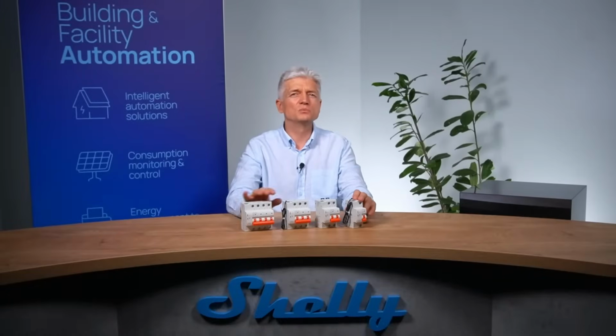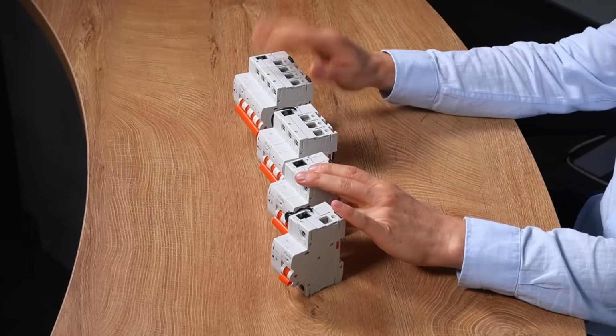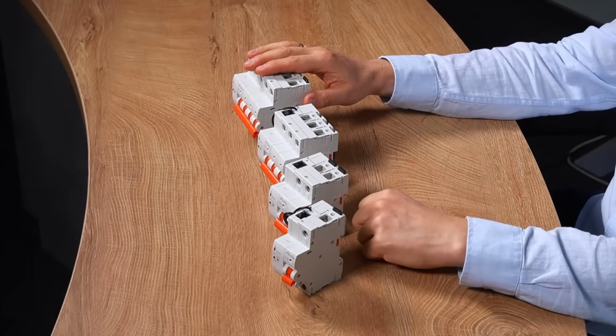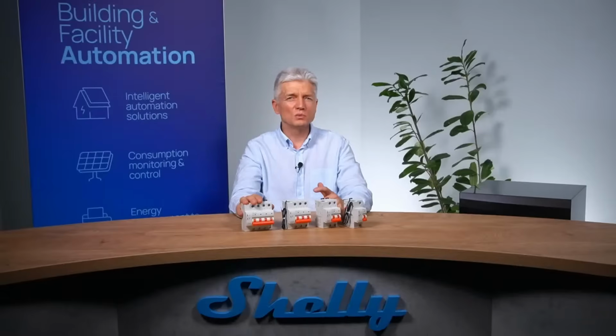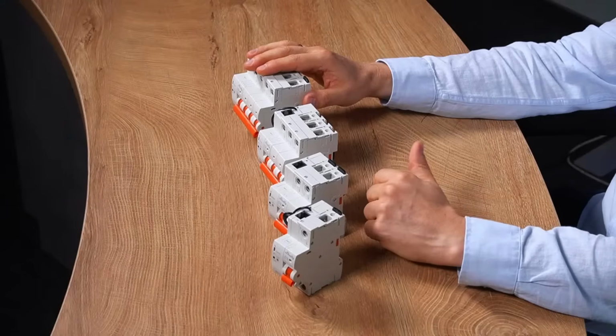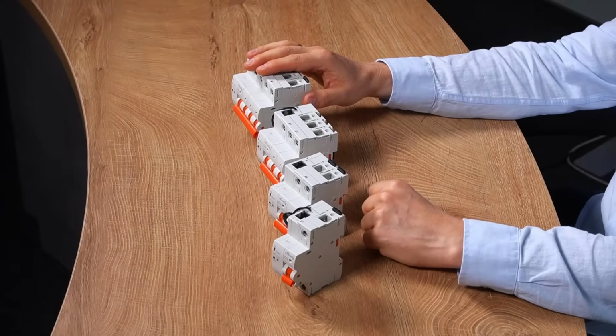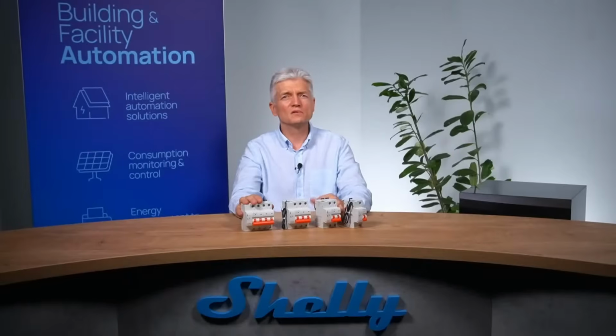Shelly Pro 1 CB and Shelly Pro 3 CB are suitable for installations where neutral overcurrent protection is not required, while Shelly Pro 2 CB and Shelly Pro 4 CB feature neutral overcurrent protection. Each model will be available with a C tripping curve and 6 tripping currents: 10, 16, 25, 32, 40, and 63 amps, thus covering a wide range of cases.